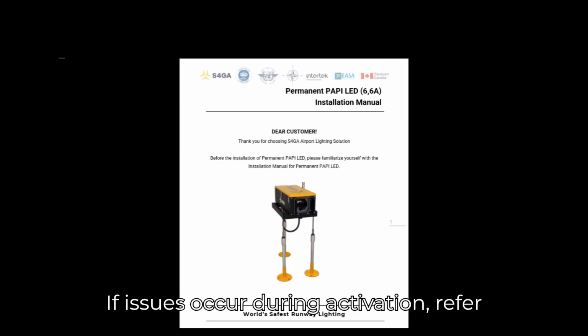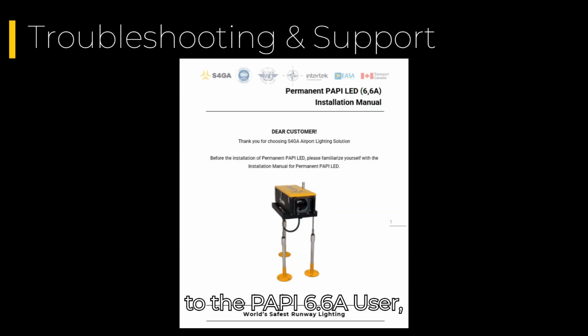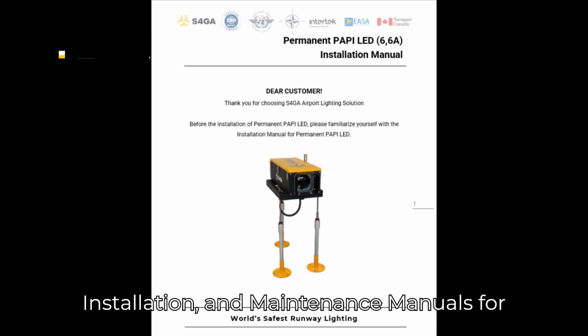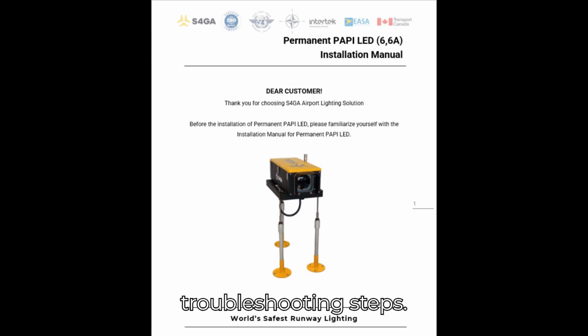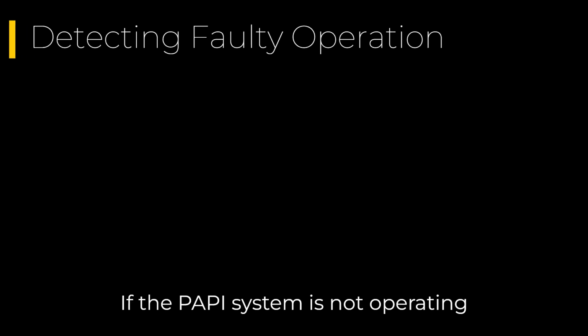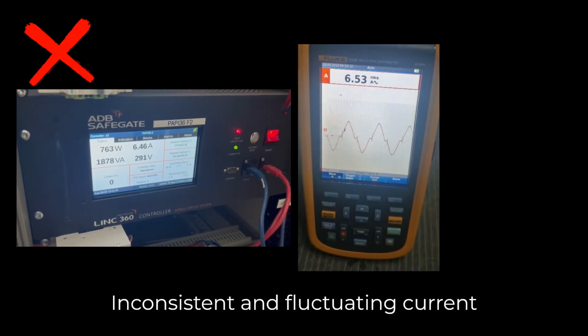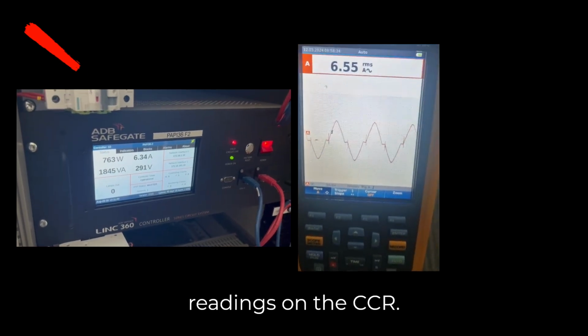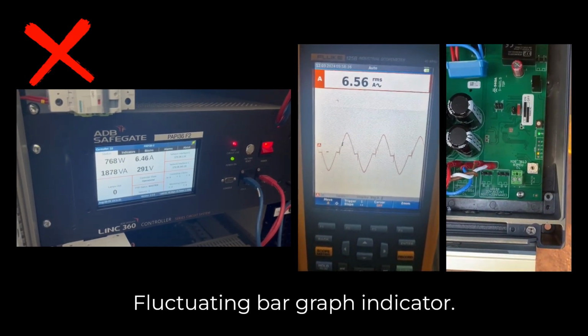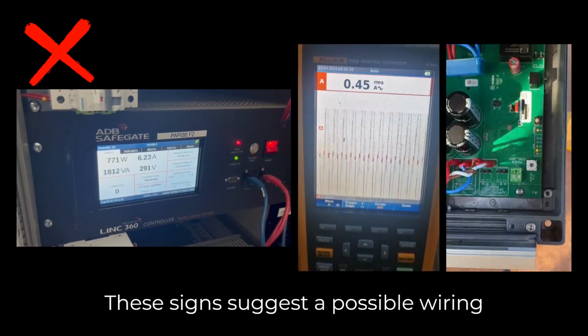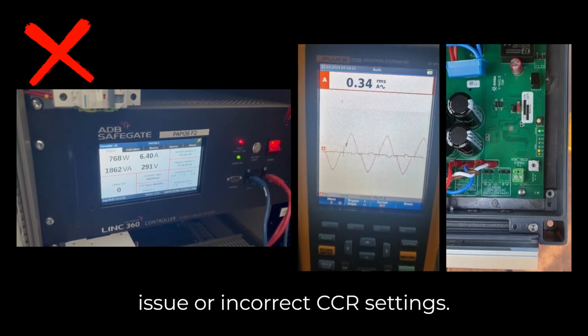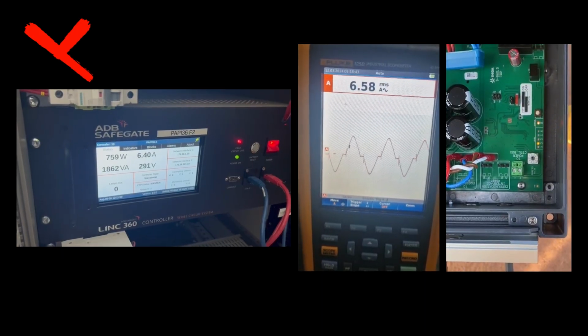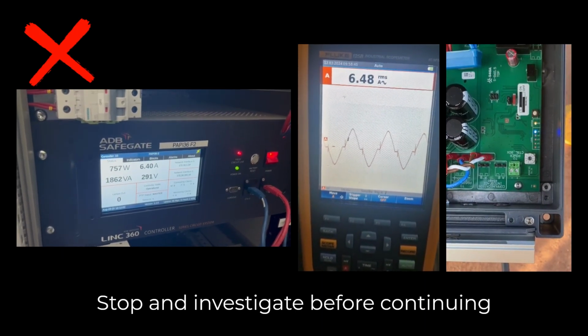If issues occur during activation, refer to the PAPI 6.6 amp user, installation, and maintenance manuals for troubleshooting steps. If the PAPI system is not operating correctly, you may notice unstable behavior, such as inconsistent and fluctuating current readings on the CCR, fluctuating bar graph indicator. These signs suggest a possible wiring issue or incorrect CCR settings. Stop and investigate before continuing operation.